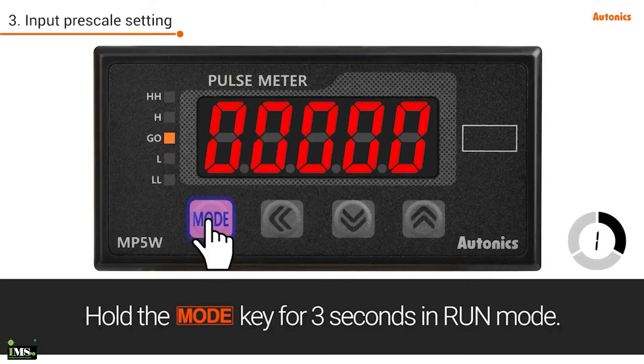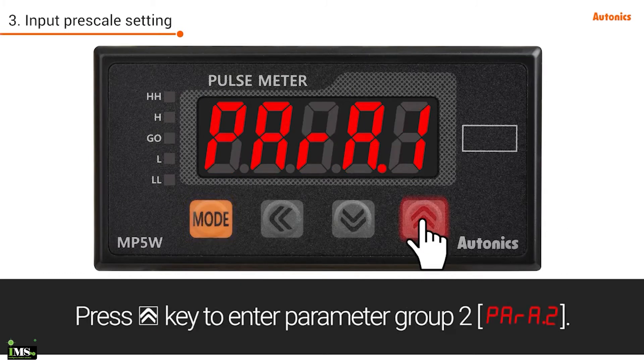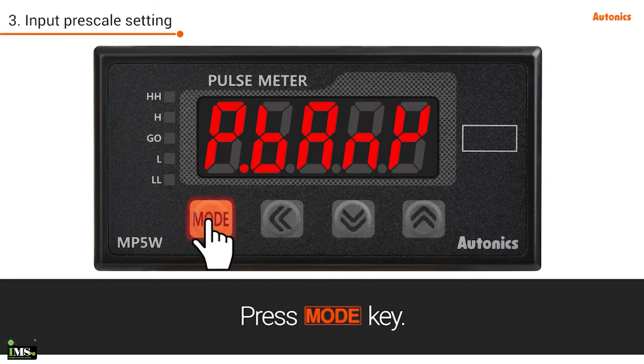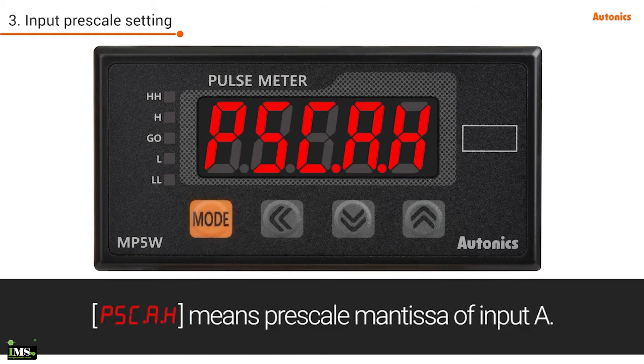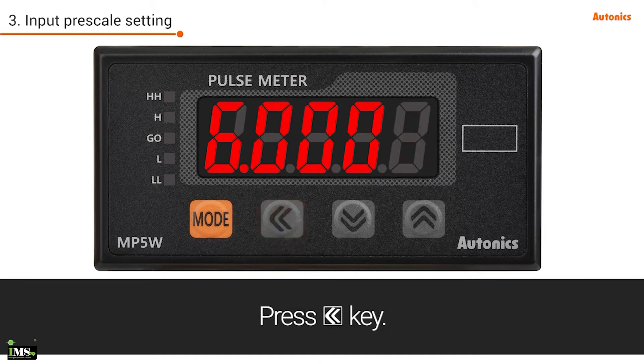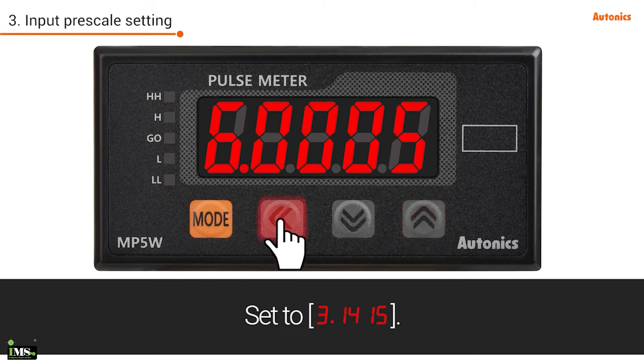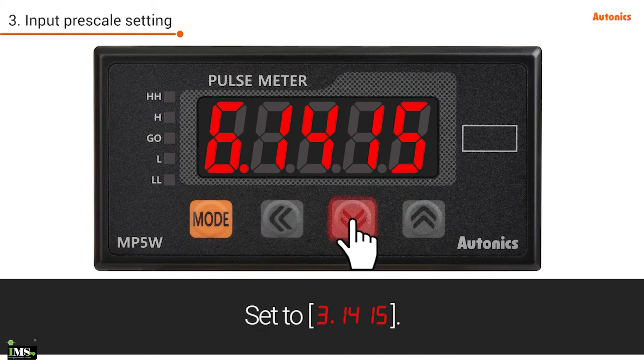Hold the mode key for 3 seconds in run mode. Press the up key to enter parameter group 2, then press the mode key. PSC.A.H means prescale mantissa of input A. Press the left key and set the value to 3.1415. Press the mode key.